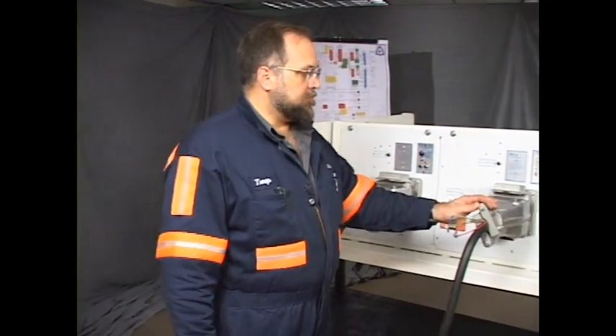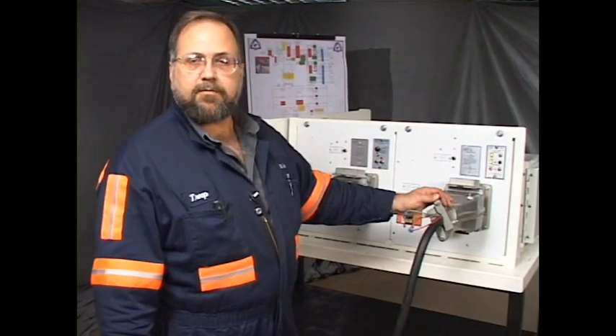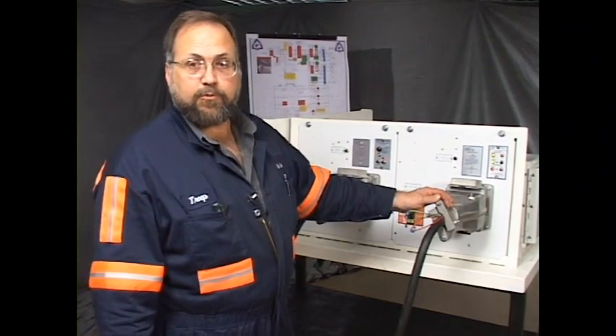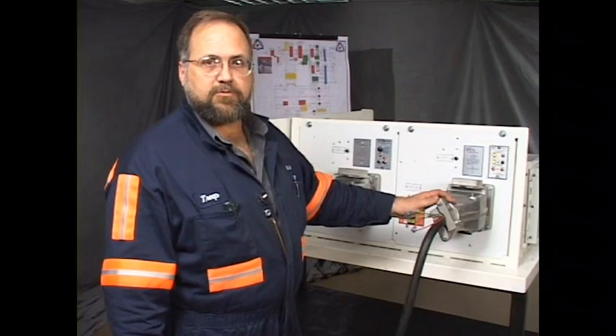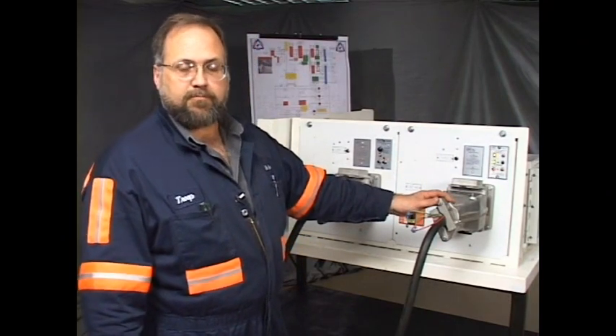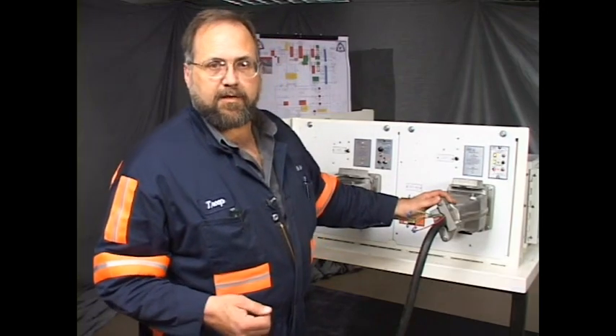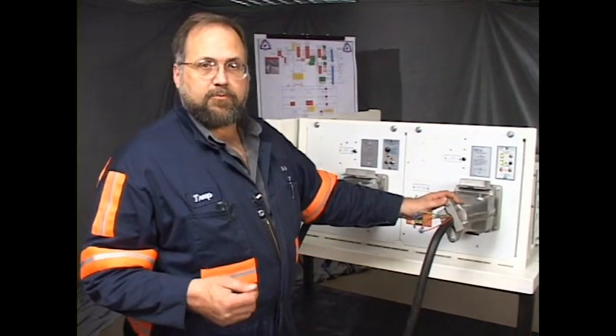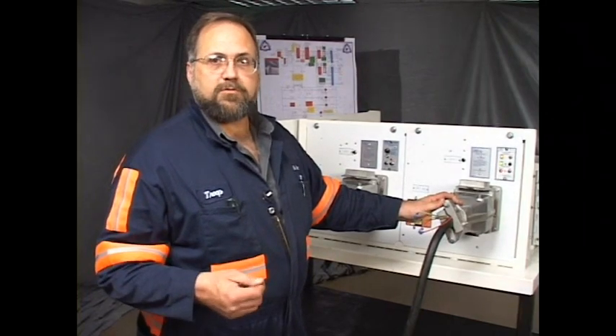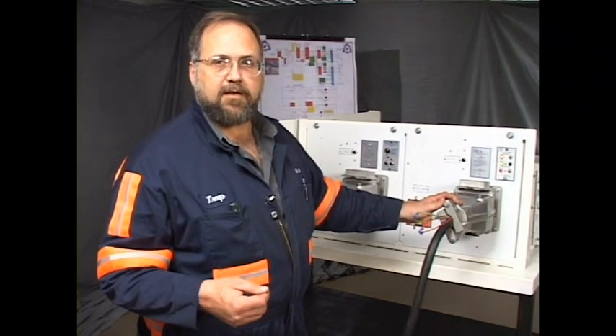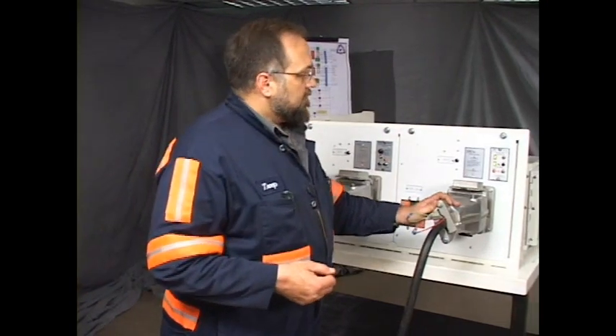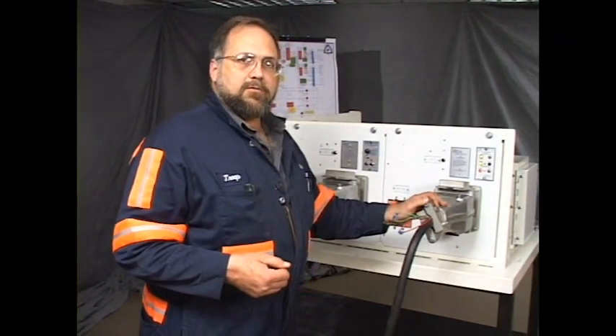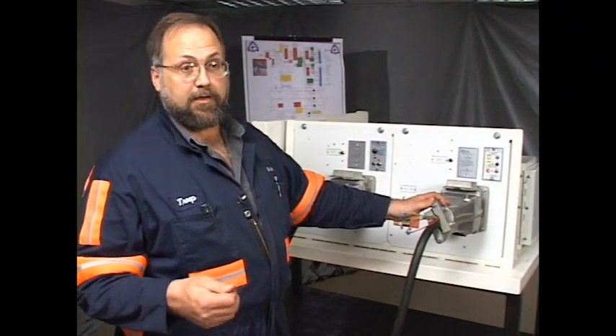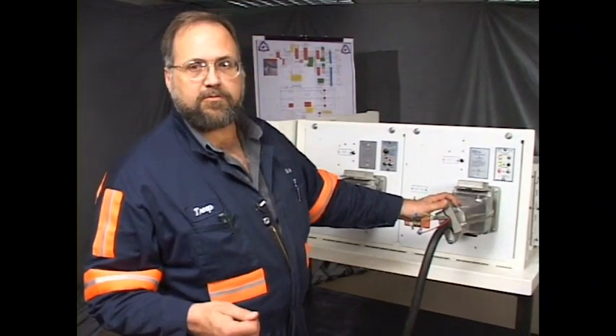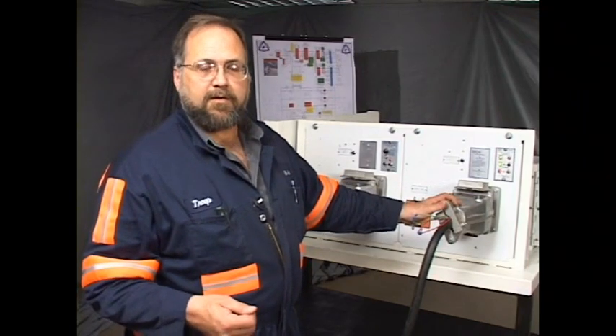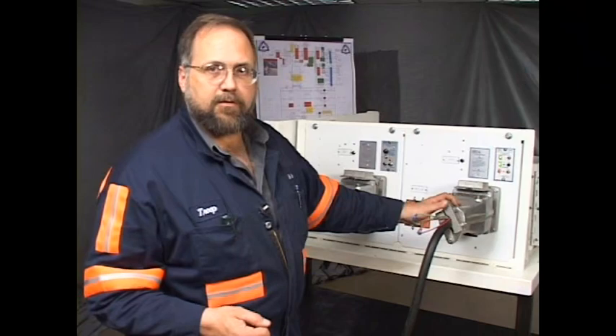On circuit number 2, you still have the relay. It's GCS number 2. It still has to be closed to put power to the UV. Those circuits are identical in that respect. What is different between the two circuits is what closes the contacts, the GCS contacts. Now, circuit number 2 employs a wireless monitor. The wire that you lose is the pilot wire. There are still wires involved, but you don't have a pilot wire dedicated only to the monitoring of the ground wire.